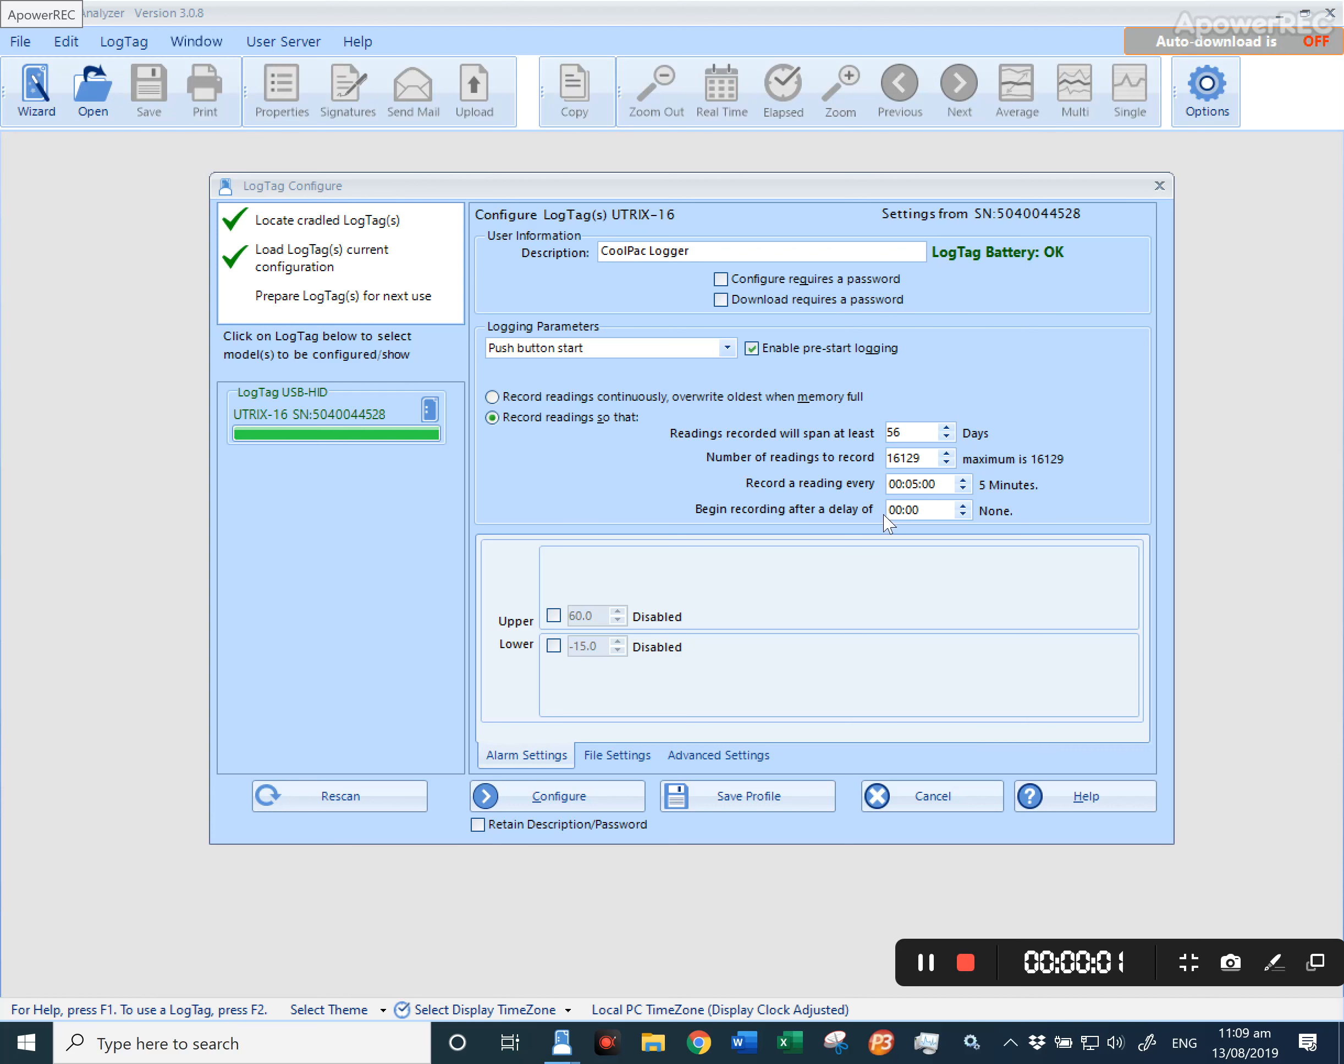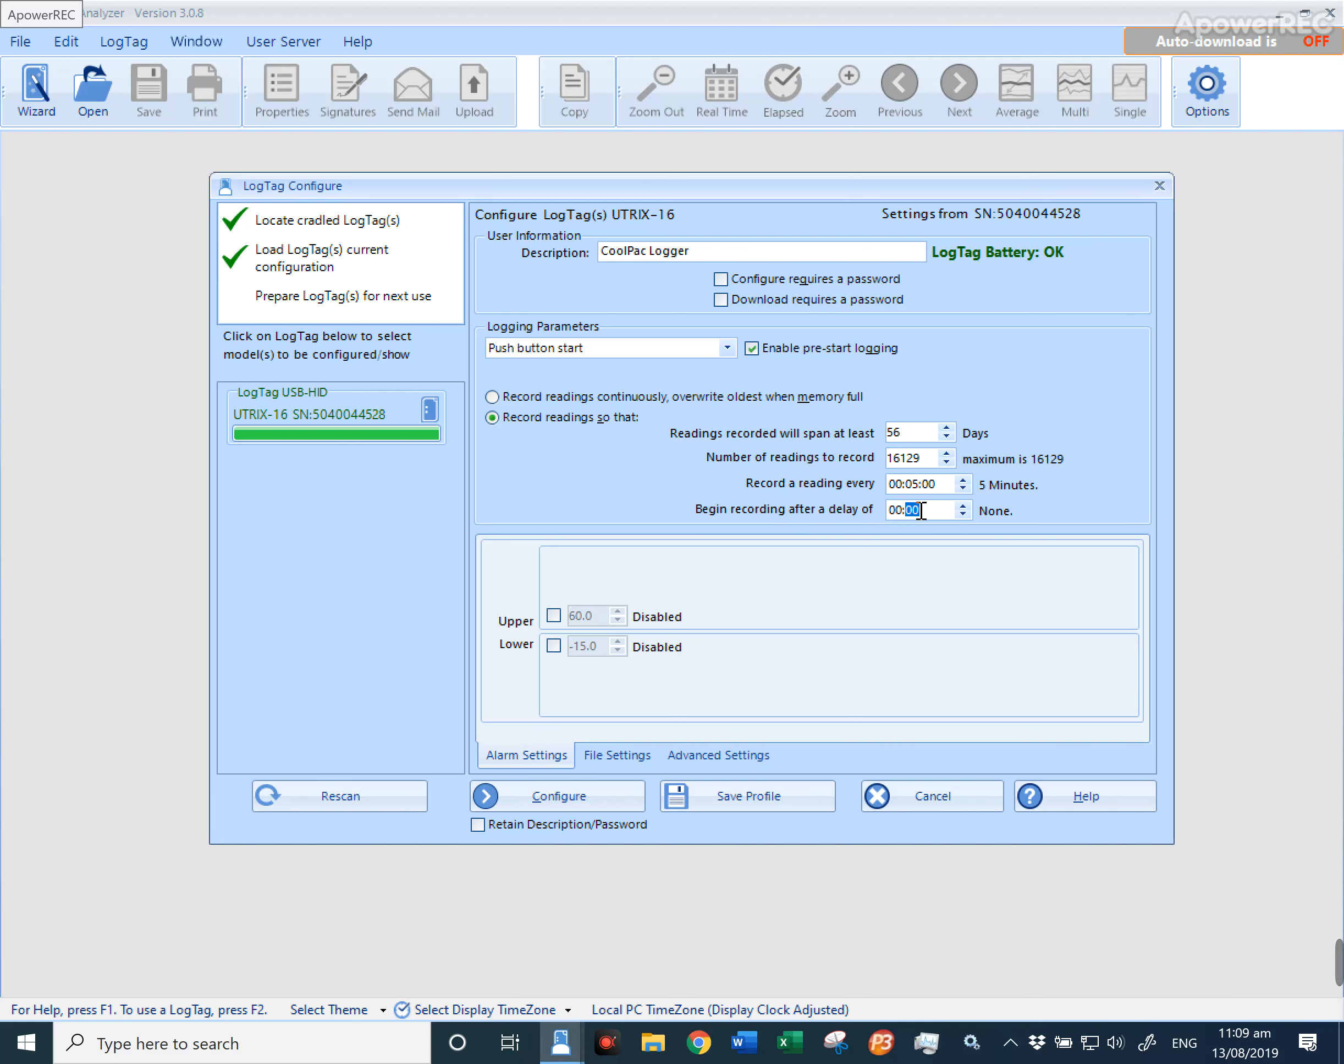The delay recording will activate once the push button has been pressed and started. For this logger, I'll configure a delay start of 30 minutes. Once that 30 minutes is up, it will begin recording every five minutes.